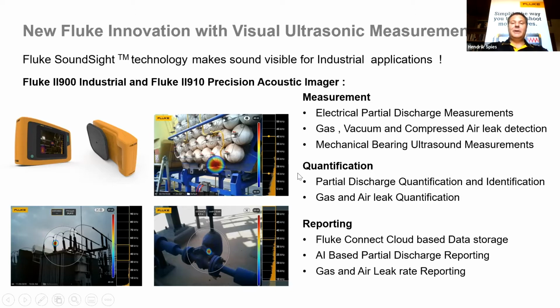So the big benefit is we can quantify, meaning if we are measuring partial discharge activity, like on this transformer, we can actually do a partial discharge count. And based on that, we can quantify the actual severity of this partial discharge, and also the type of partial discharge that is actually present on the asset. On the gas and air leak detection, we have leak quantification, which, if you see this photo, we measure the distance, and we've got a severity scale built into our unit. And the reporting is quite phenomenal on the product.